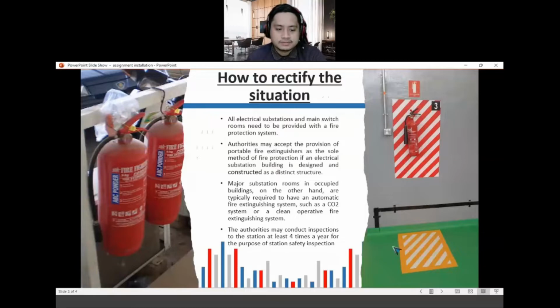So if there is any fire in the electrical system, the automatic fire extinguisher system can turn on automatically. So there is no need for people, and it can save time for the fire department to arrive at the substation. The last but not least, the authorities may conduct inspections of the substation at least 4 times a year for the purpose of substation safety inspection. For example, they can come to the substation to check whether there is a fire extinguisher that the owner put in the substation, or they can also check the expiry of the fire extinguisher to tell the owner the fire extinguisher needs to be changed for a new one.